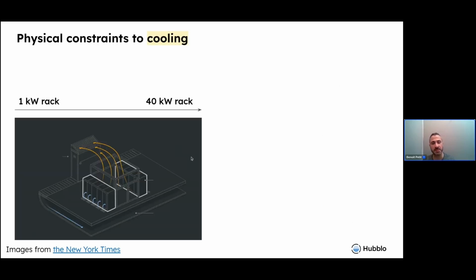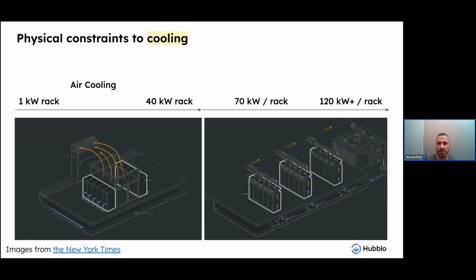To be more complete about AI cooling, there is still another issue, which is a physical constraint to cooling. If you have racks that are up to 40 kilowatt per rack in terms of power intensity, it's okay to use air cooling. It will work. But above 40 kilowatts per rack, you physically need to change the cooling system. You have to go for liquid cooling. Between 40 kilowatt per rack and 70, it might work with door cooling, which is an intermediate system that relies on liquid cooling, but the circuit stops at the door. And then the air that's cooled thanks to the liquid cooling system is pushed inside the rack through fans. And after 70 kilowatt per rack, you will need direct liquid cooling, which means direct liquid cooling to chip. You will need to have contact through a surface that's directly on the chip itself.